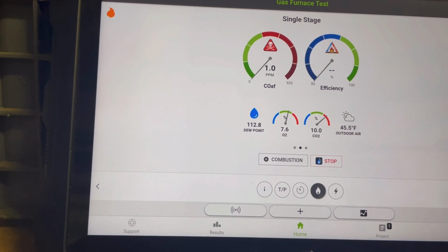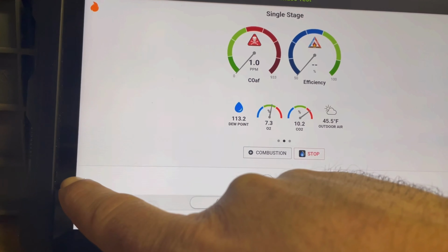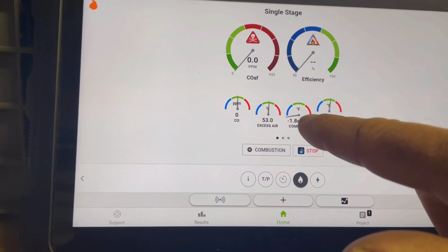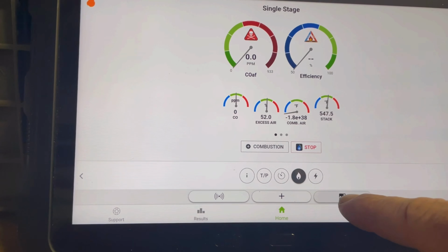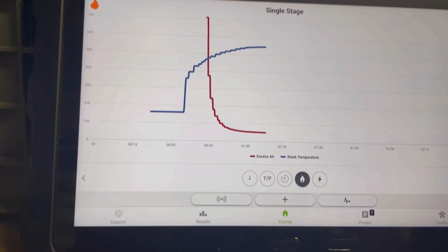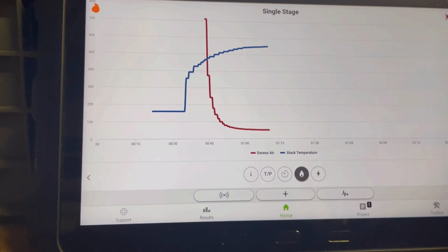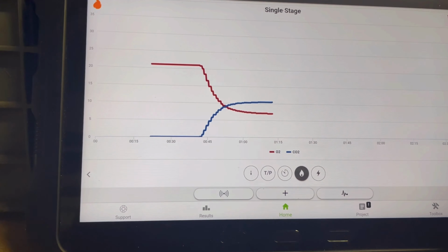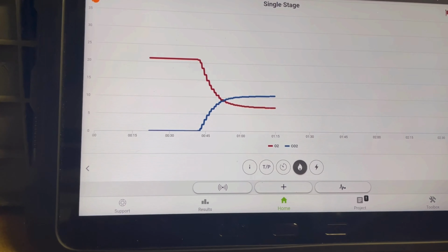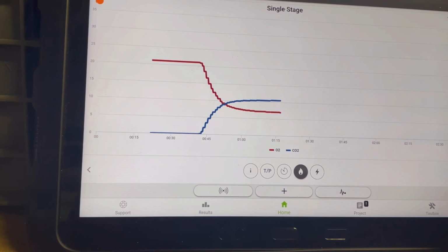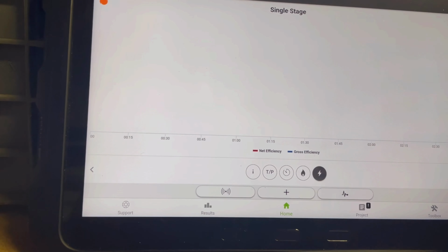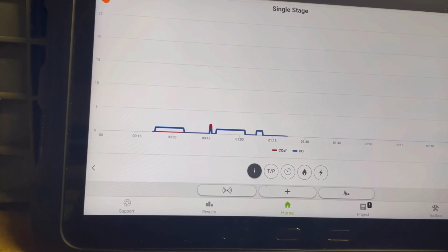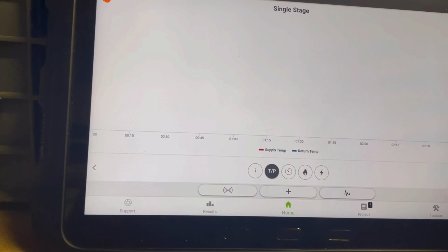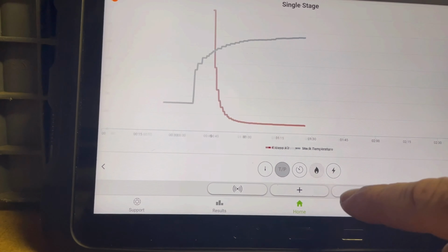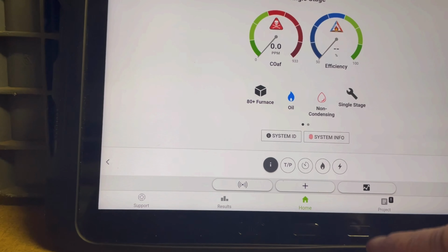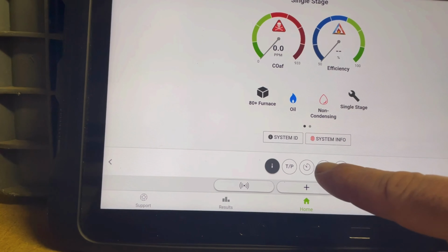As you saw on the Testo 300 with the graphs, MeasureQuick has that ability to do the same thing in their application. Why is that so important? Well, I've witnessed technicians that need to be more patient. They need the equipment to run a little bit longer to stabilize, and that's what the graph shows. Oftentimes I see technicians rush through, and maybe they get an incorrect reading, and they make a bad decision from that. So it's pretty cool that the information can be broadcast over into MeasureQuick.